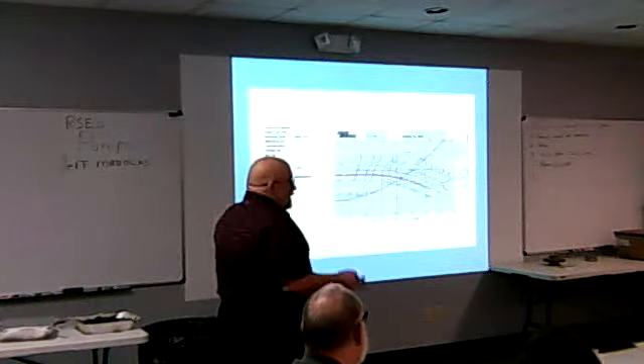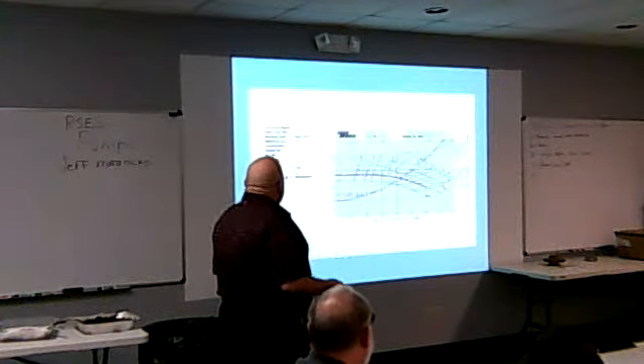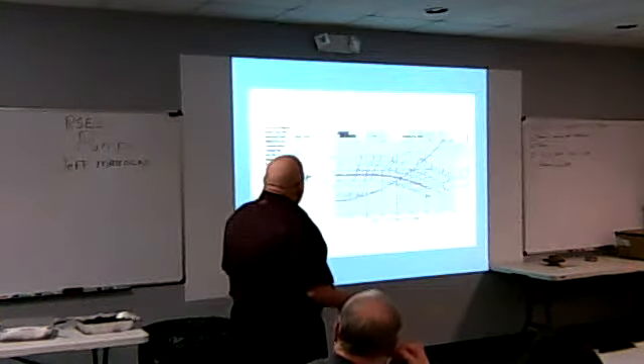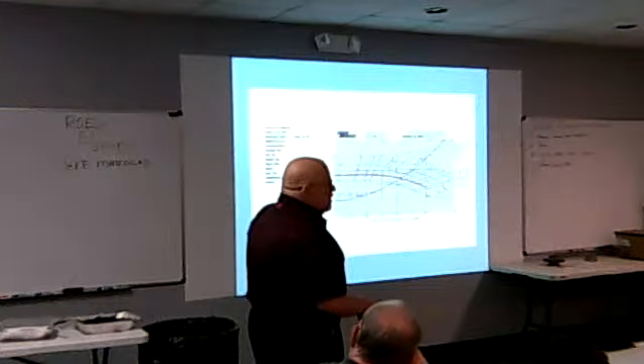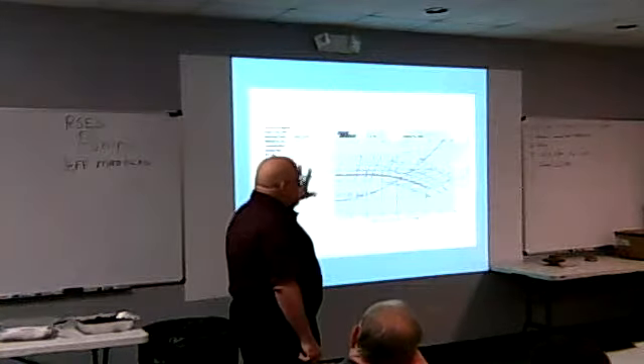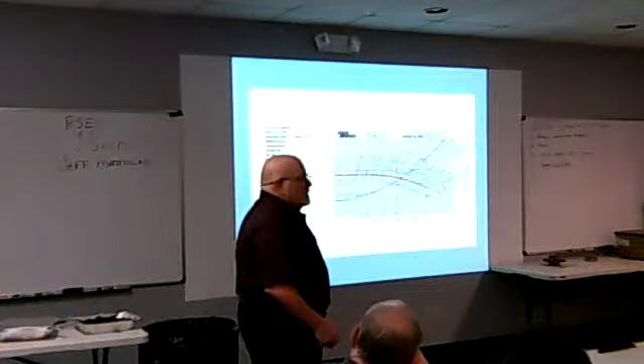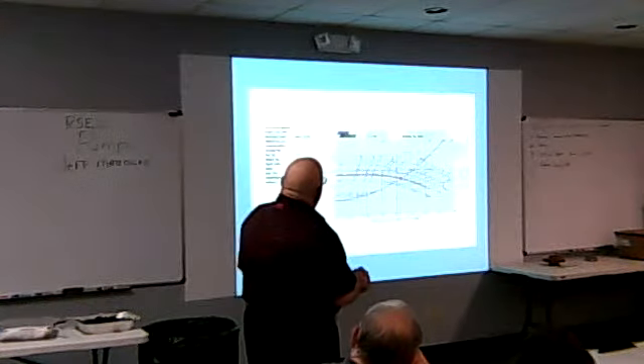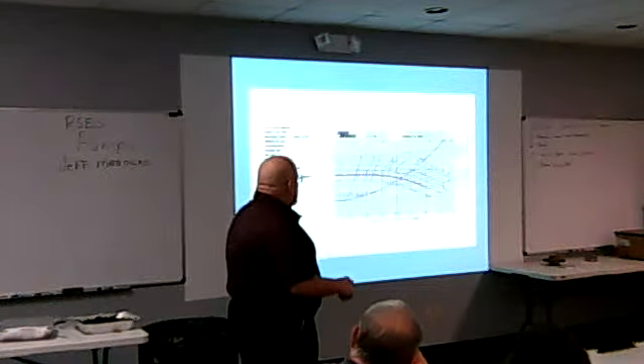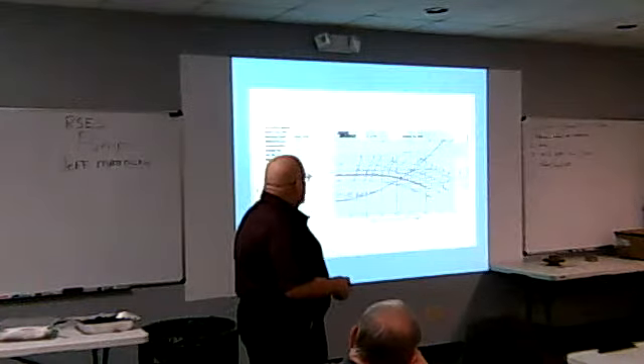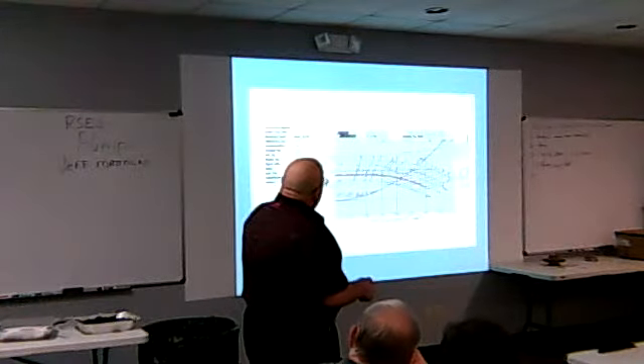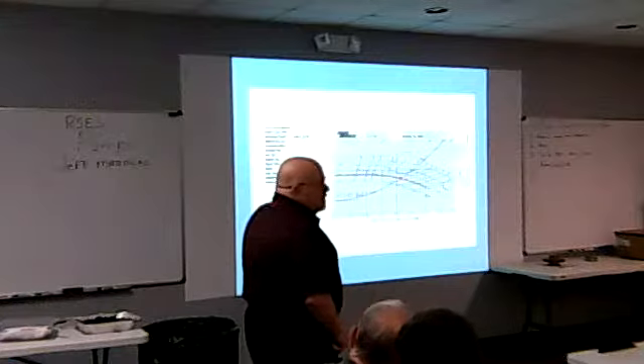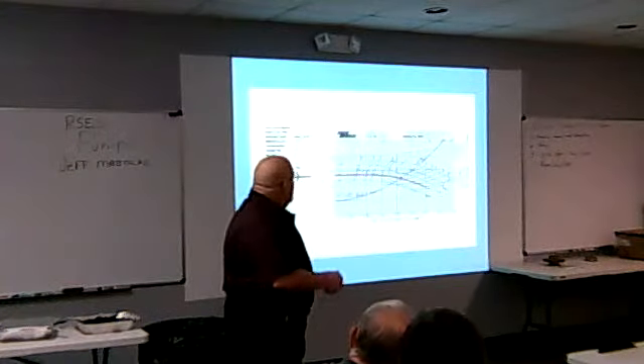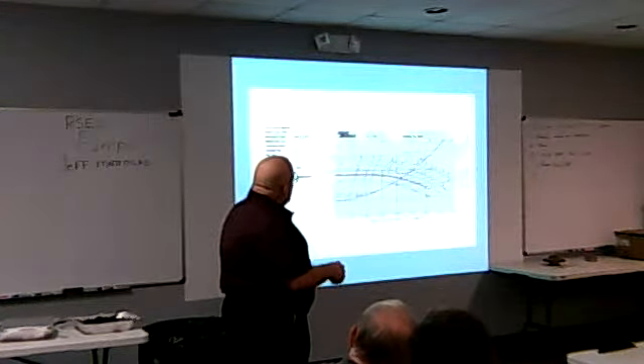Okay, this is a pump curve. Everybody seen one of these before? Very simple. This is our flow for any pump. These are all generated by a factory on every pump you select. This is your head in feet. You can get them in meters or liters per second, but this is English. And you see a little dot there. That's your operating point. And what you have in the curves, you got flow, head.